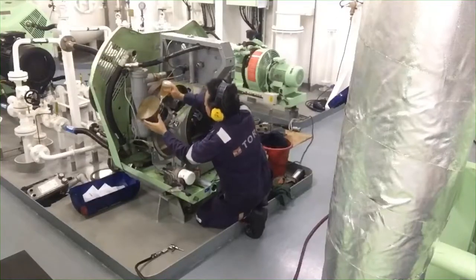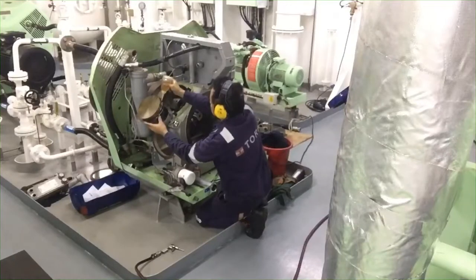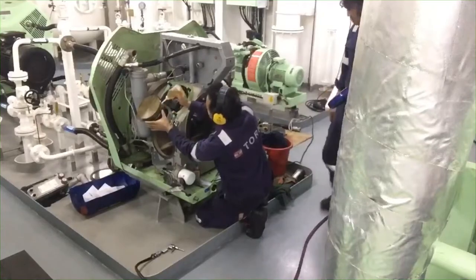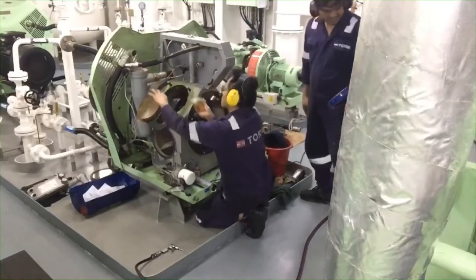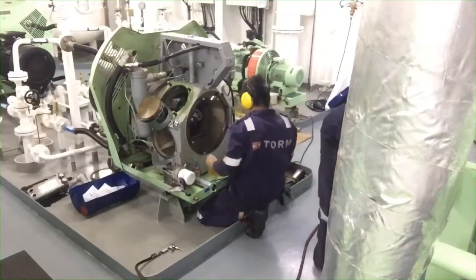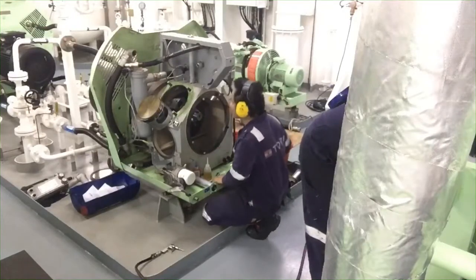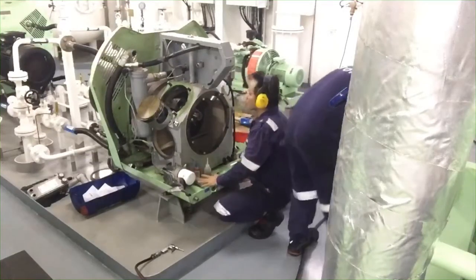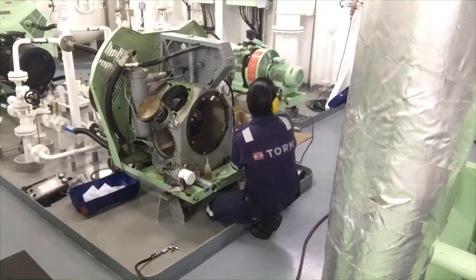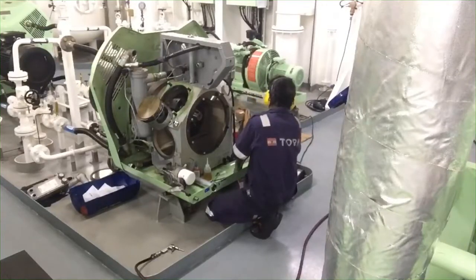The problem there that I uploaded is to change this crankshaft, because the crankshaft before had a problem of lubrication. That's why the crankshaft is totally damaged. So I have already uploaded that video in my channel about the Tanabe compressor, on how to change this crankshaft on Tanabe.